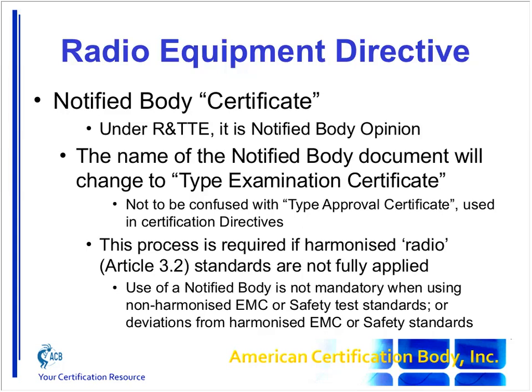And if the standard you're using for radio performance is not listed on the official journal, then you must use a notified body. Now, here's a change from the R&TTE directive: use of a notified body is not mandatory when using non-harmonized EMC or safety test standards.